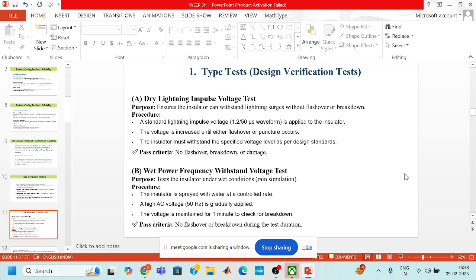Now, second is the wet power frequency withstand voltage test. The main purpose of this test is to check the insulator under wet conditions, like a rain simulation condition. First of all, the insulator is sprayed with water at a controlled rate, and a high AC voltage at 50 Hz is gradually applied, and the voltage is maintained for 1 minute to check for breakdown. Okay.